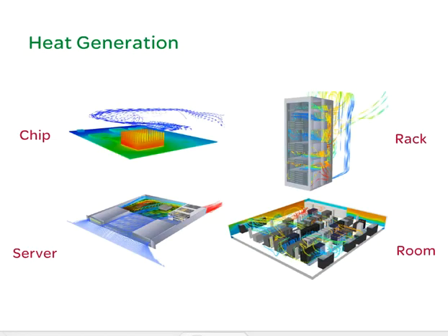Wherever electrical power is being consumed in an information technology room or data center, heat is being generated that needs to be removed from the space. This heat generation occurs at various levels throughout the data center, including the chip level, server level, rack level, and room level. With few exceptions, over 99% of the electricity used to power IT equipment is converted into heat. Unless the excess heat energy is removed, the room temperature will rise until IT equipment shuts down or potentially even fails.